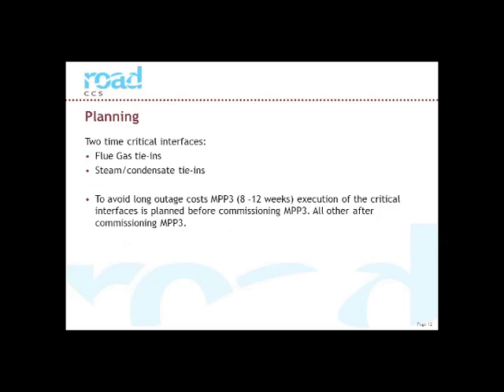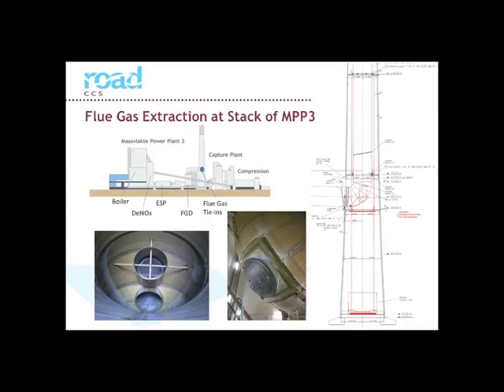There were two time-critical interfaces. At first, the flue gas tie-ins, and secondly, the steam and condensate tie-ins. We decided to execute those tie-in works before the commissioning of MPP3 started, because during commercial operation it will be too costly to plan a very long outage to execute those tie-in pieces. The first work that was executed in 2012 were the flue gas tie-ins.